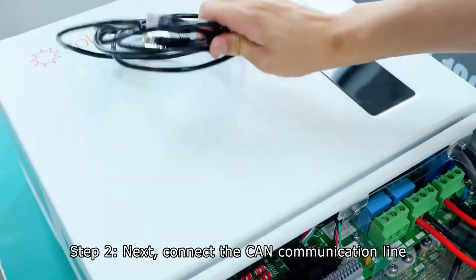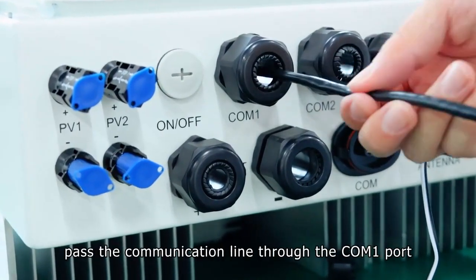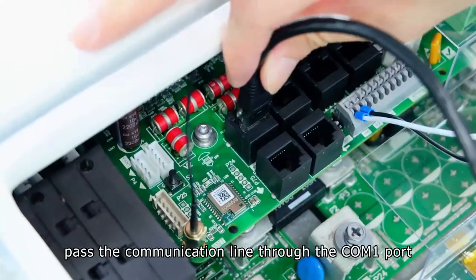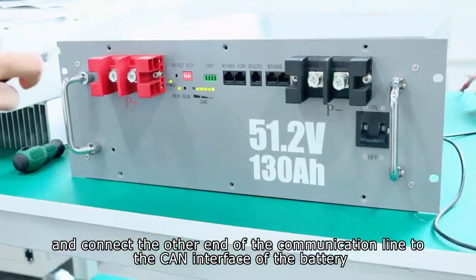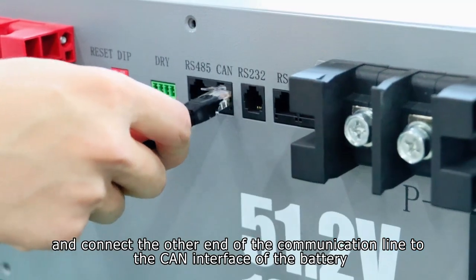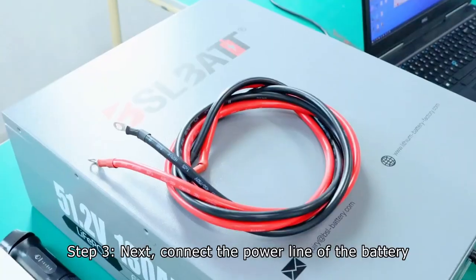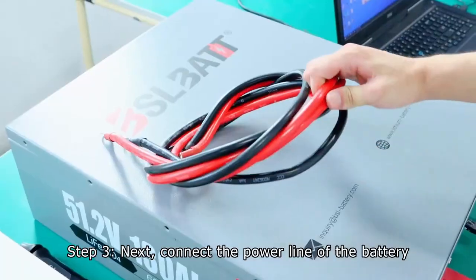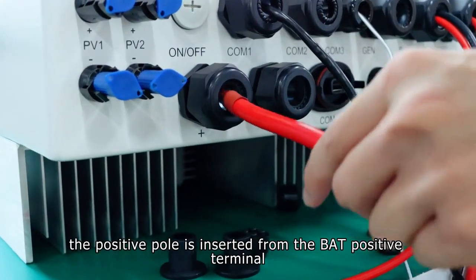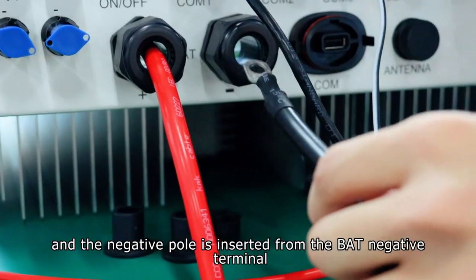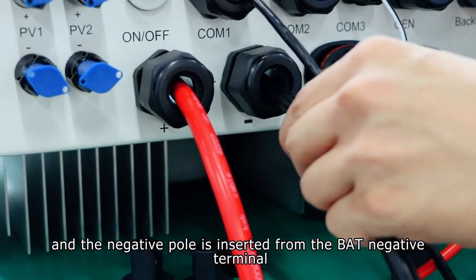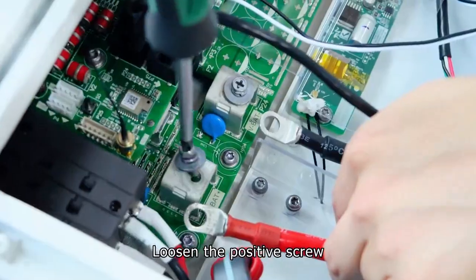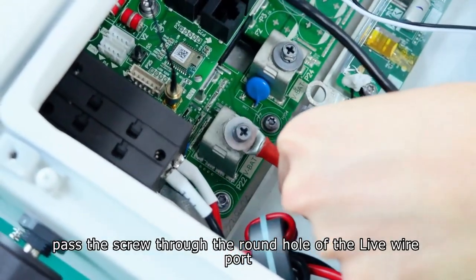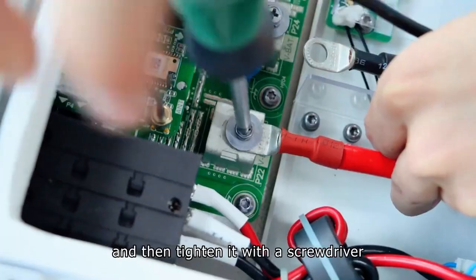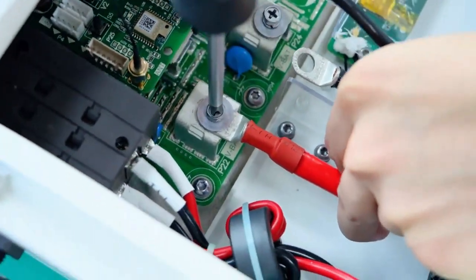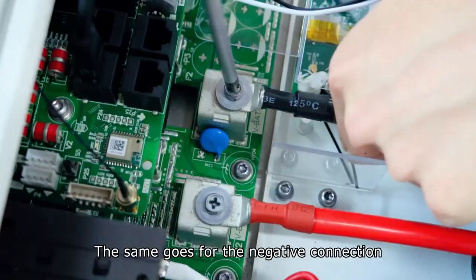Step 2. Next, connect the CAN communication line, pass the communication line through the COM1 port, and insert it into the first port, and connect the other end of the communication line to the CAN interface of the battery. Step 3. Next, connect the power line of the battery. The positive pole is inserted from the BAT positive terminal, and the negative pole is inserted from the BAT negative terminal. Loosen the positive screw, pass the screw through the round hole of the live wire port, and then tighten it with a screwdriver. The same goes for the negative connection.